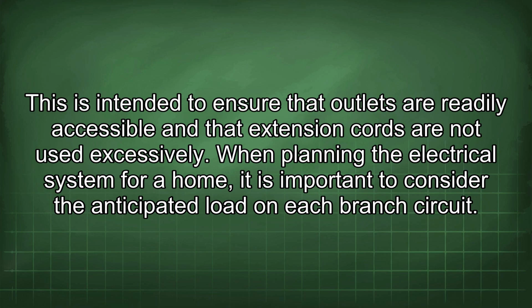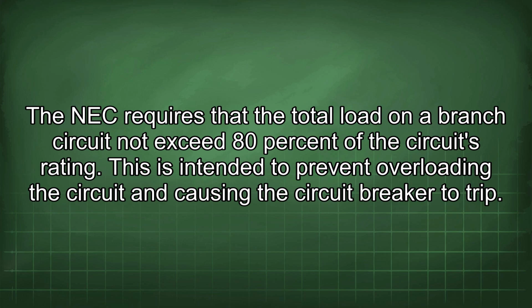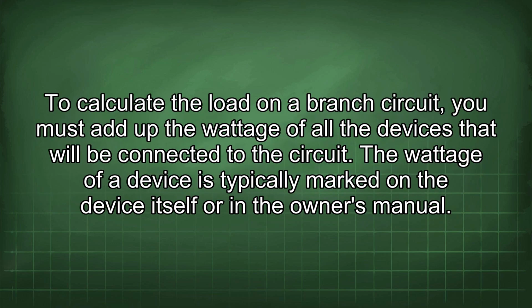When planning the electrical system for a home, it is important to consider the anticipated load on each branch circuit. The NEC requires that the total load on a branch circuit not exceed 80% of the circuit's rating. This is intended to prevent overloading the circuit and causing the circuit breaker to trip. To calculate the load on a branch circuit, you must add up the wattage of all the devices that will be connected to the circuit.